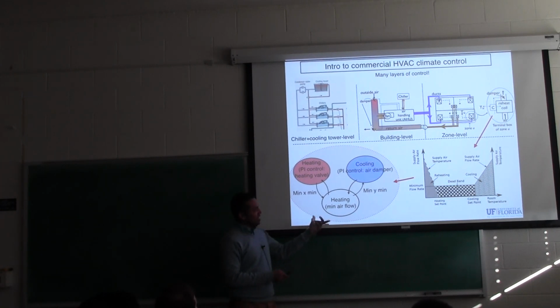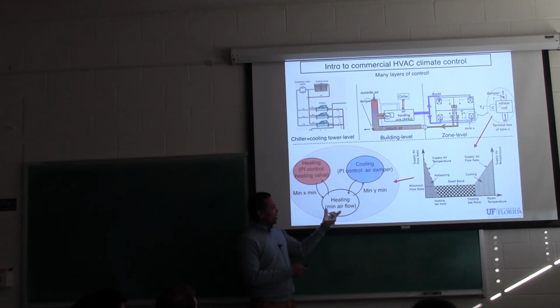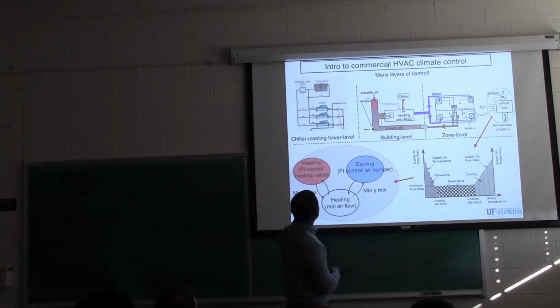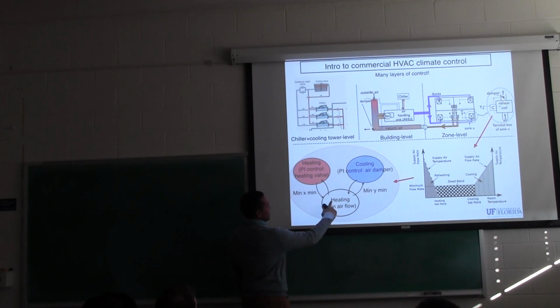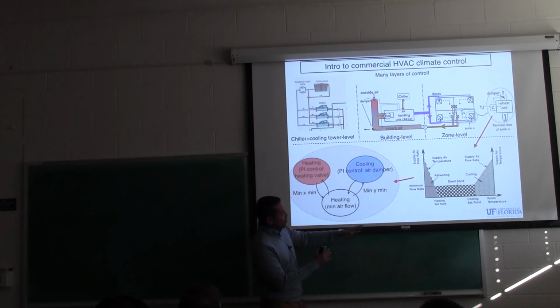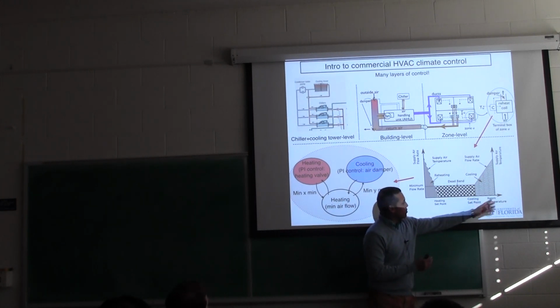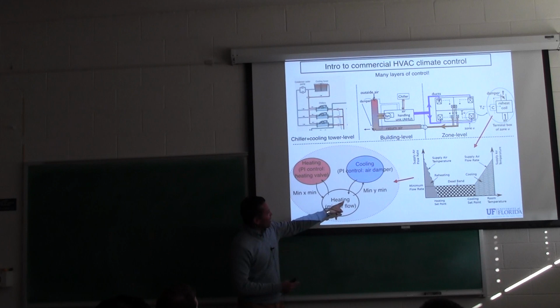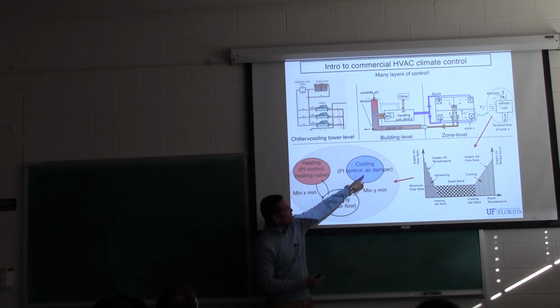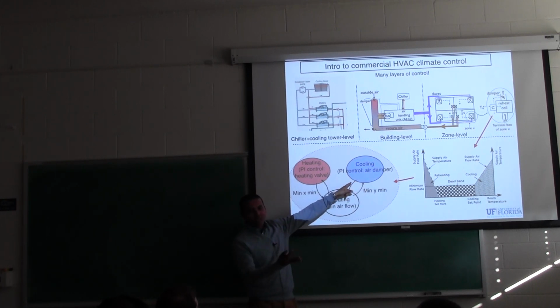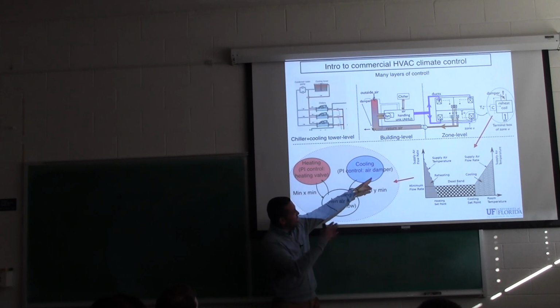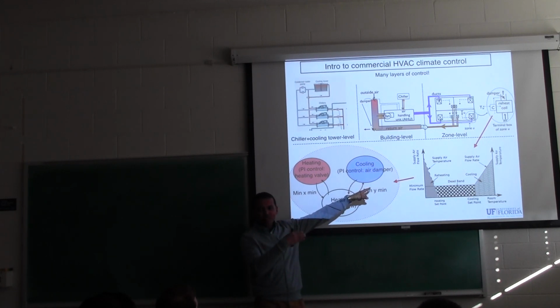Actually what is happening is that this is a hybrid dynamical system. Once you have a deadband mode, okay, there's a typo. This is not heating, this is deadband. In a deadband, it maintains a minimum airflow. Once the temperature crosses this set point and becomes too hot, then the system switches to the cooling mode. In cooling mode, it uses a different PI controller to change the airflow rate to bring the temperature back.